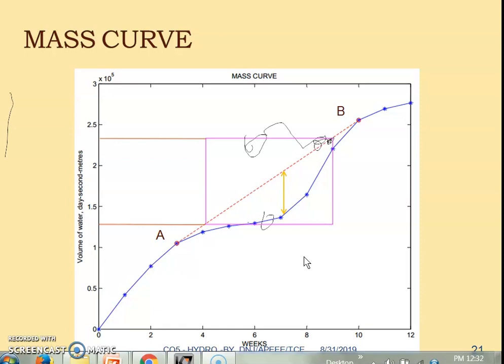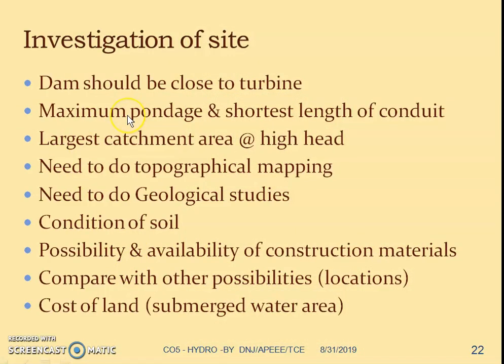Now we will discuss site selection for hydroelectric power plants. With respect to site investigation, three prime things to identify are: the dam should be very close to the turbine; you need a maximum quantity of water at a higher altitude; and you need to find a place for the turbine such that the shortest length of conduit is arranged. The conduit is the channel that conducts water from the reservoir to the turbine, essentially a pipeline arrangement between the reservoir and the turbine.